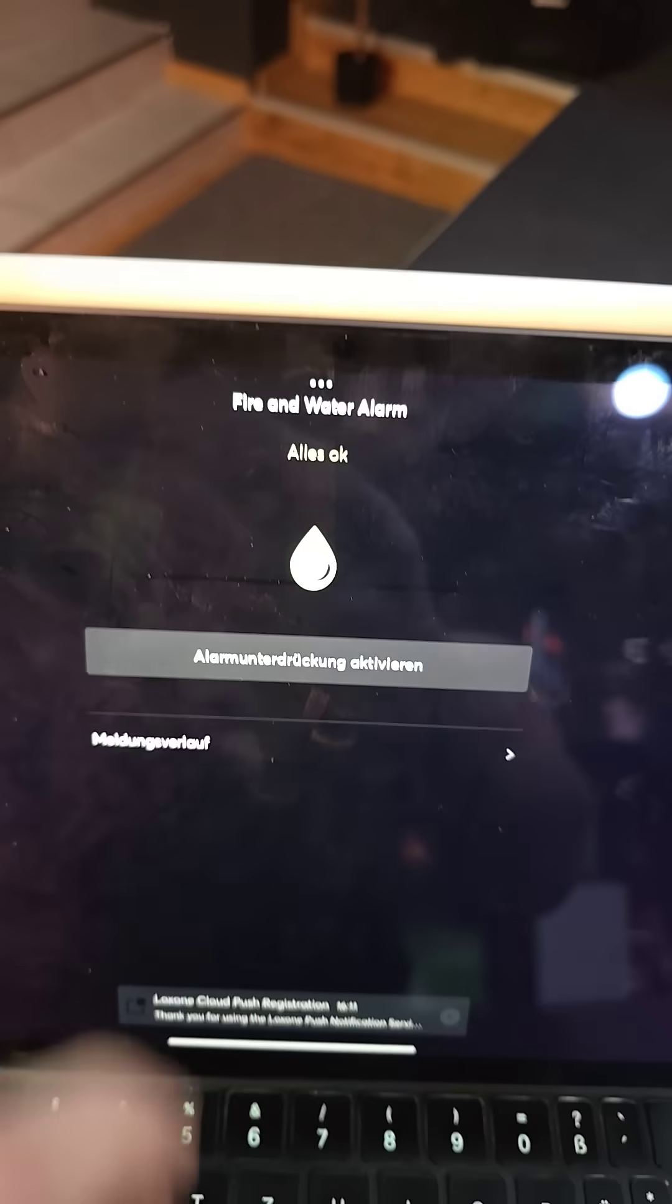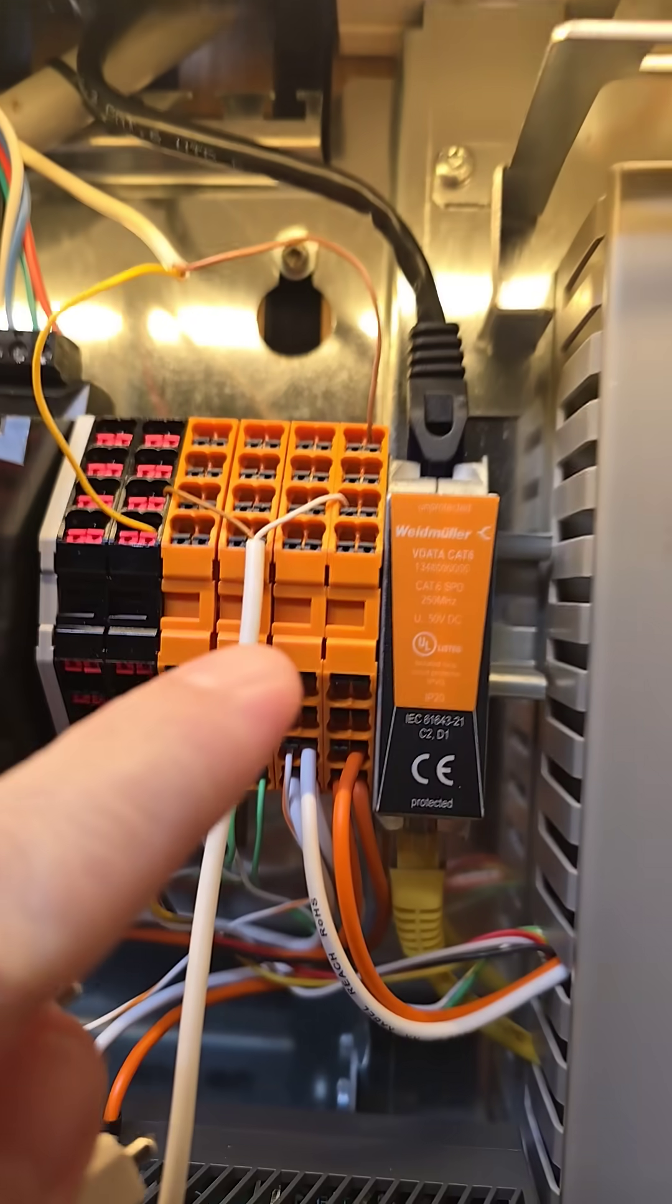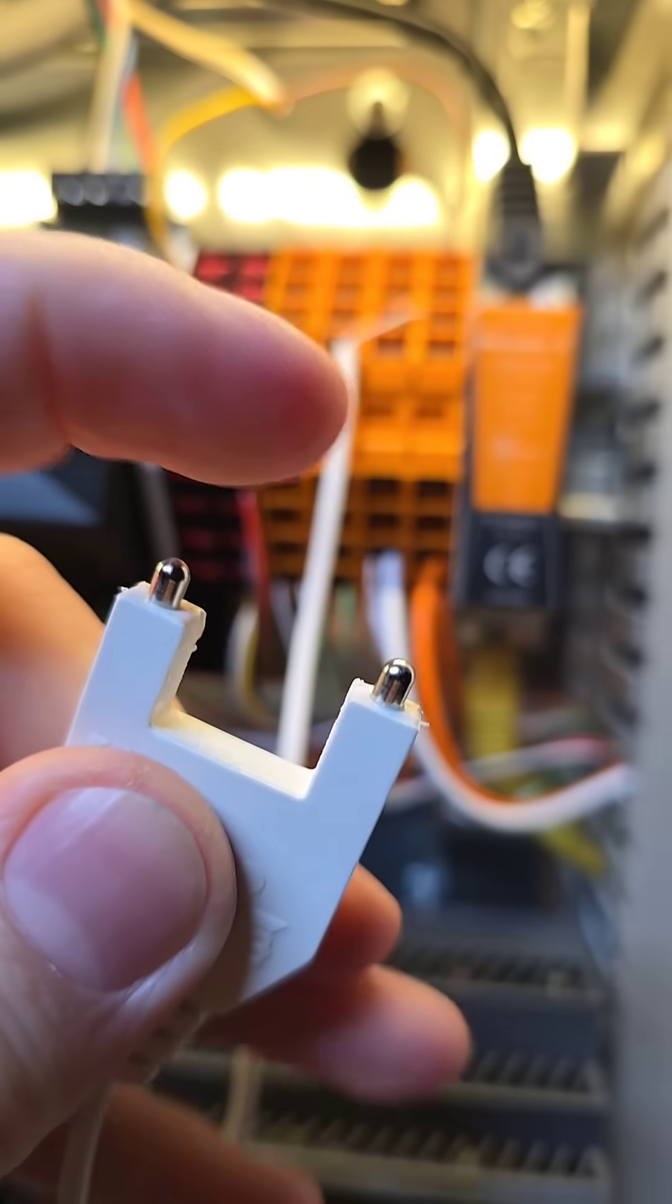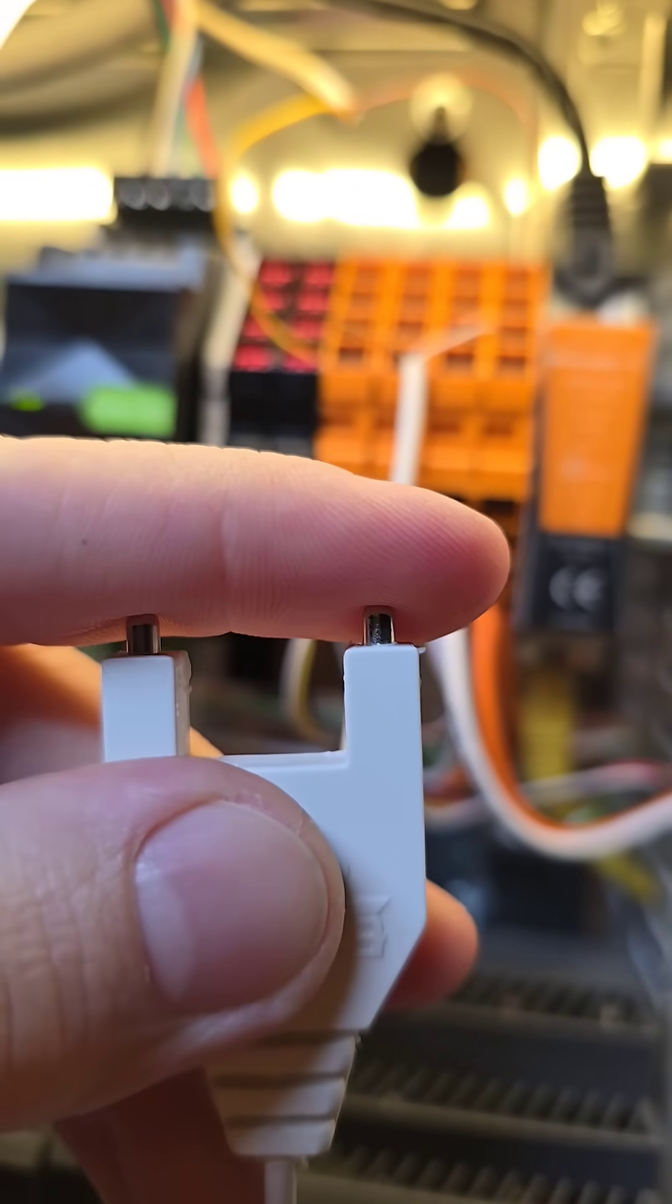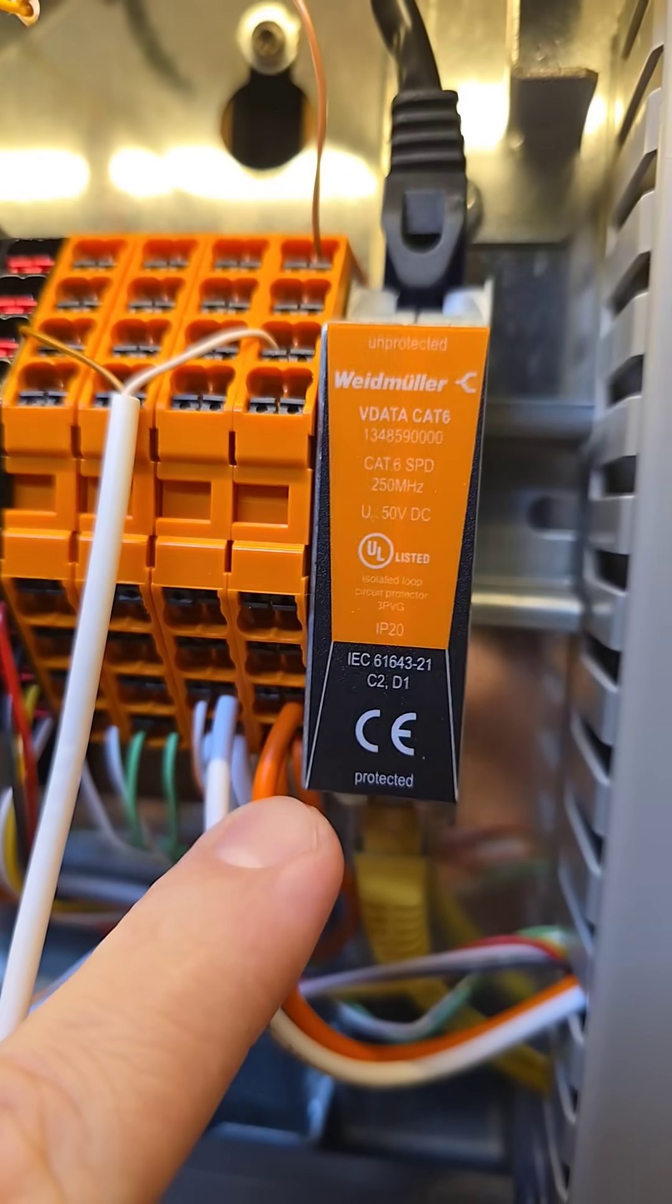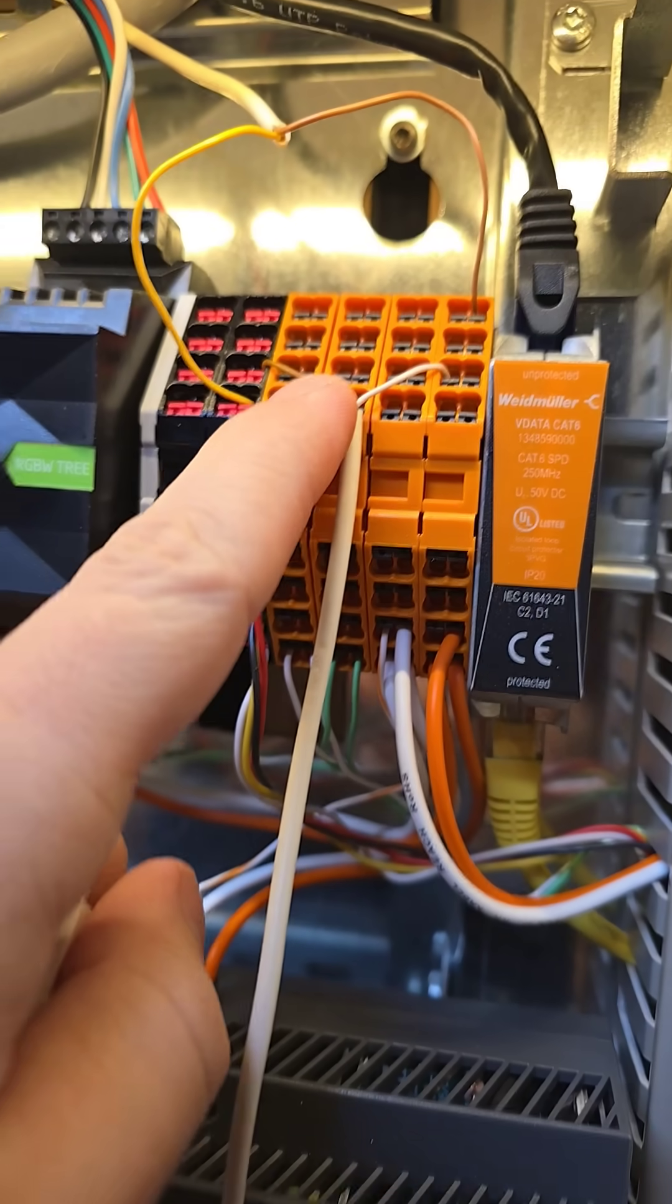Let me stop this one. The sensor is super simple - it just has two wires, and if there is water between those contacts here, it bridges the connection. So what I did here is I put 24 volt permanent power on the white one, and put the second one so in case of an alarm, the 24 volt comes out on the brown one here and goes down to my mini server on a 24 volt input.